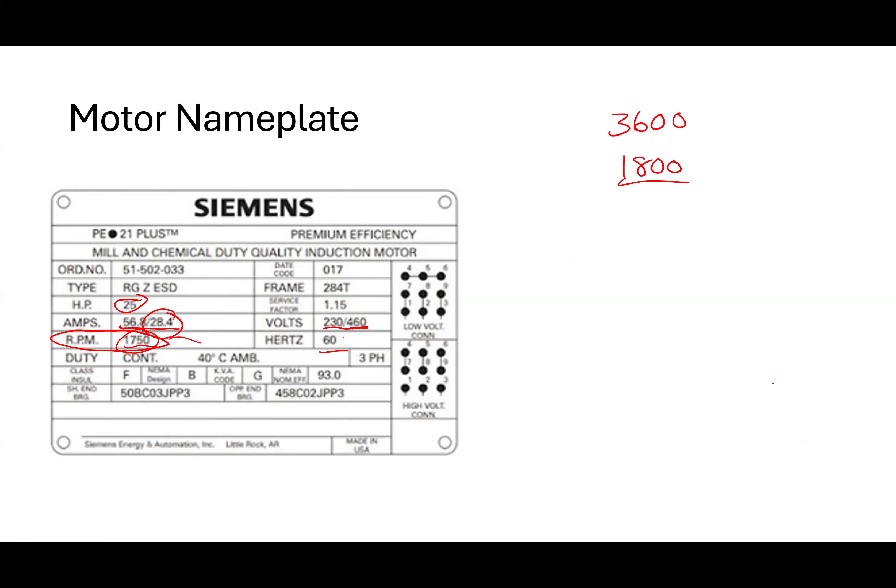Sometimes induction motors are called constant speed motors because they don't change speed much perceptibly — to go from no load to full load is a minimal change in speed. For a small motor, a one-horsepower motor, it's probably at like 1700. But for a large, serious motor, I've seen it be as high as 1780 for an 1800 RPM machine. What we refer to that as is how much it slips — how much it basically falls behind what its full speed rating is.